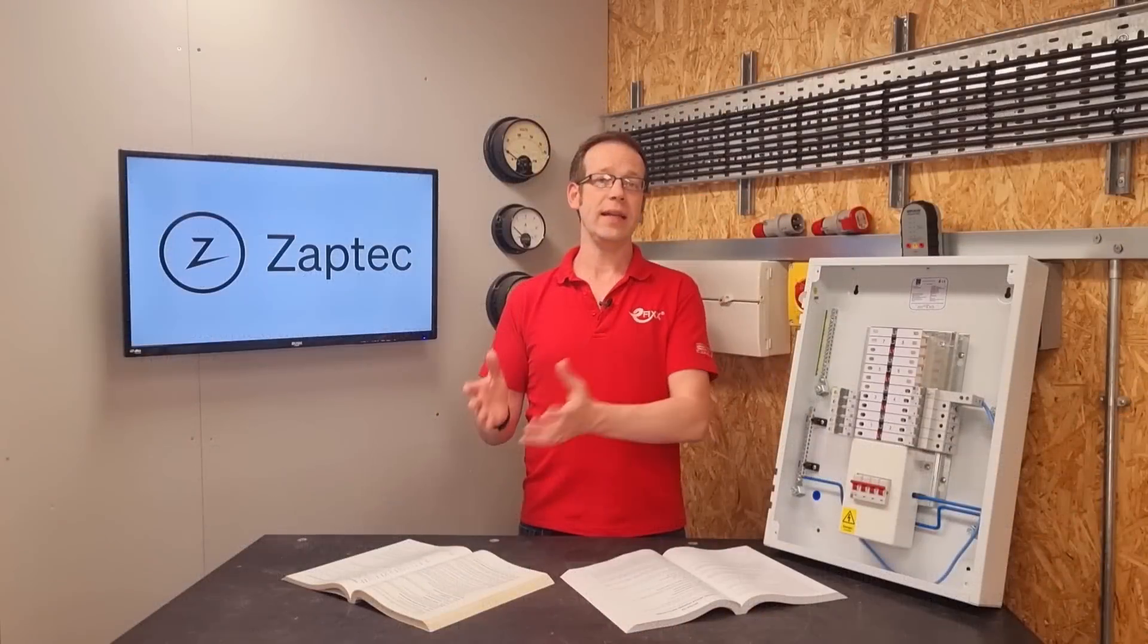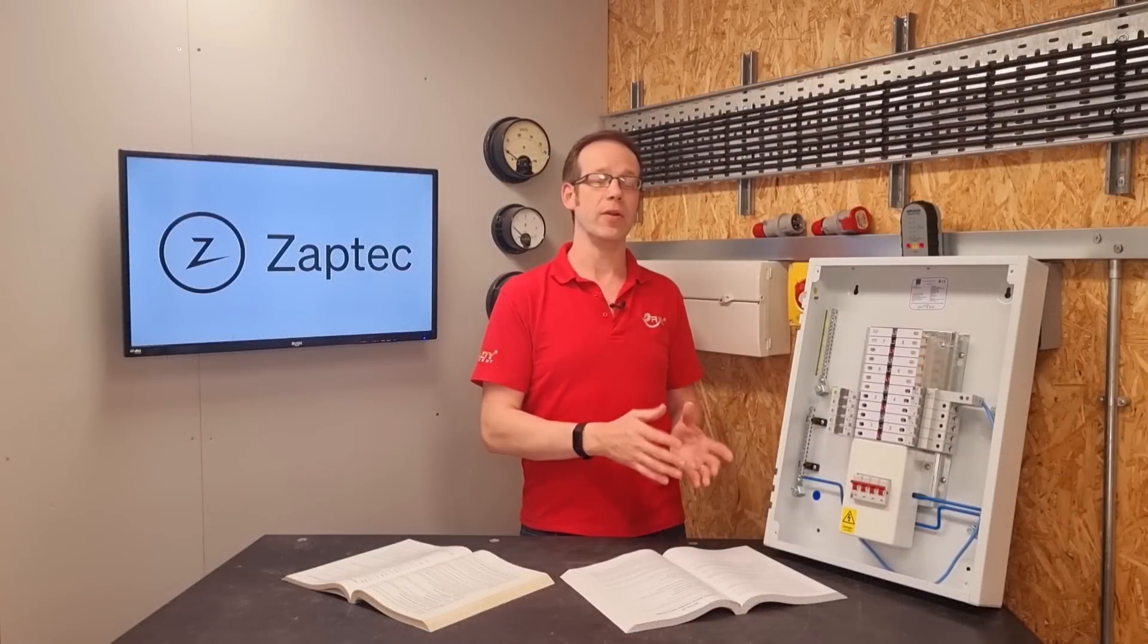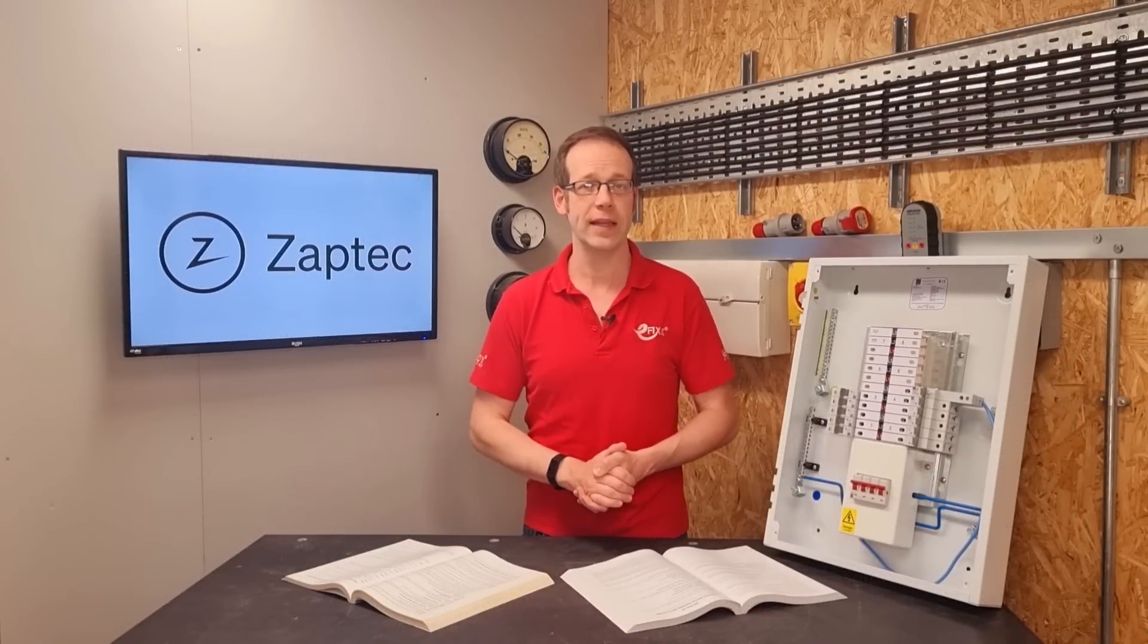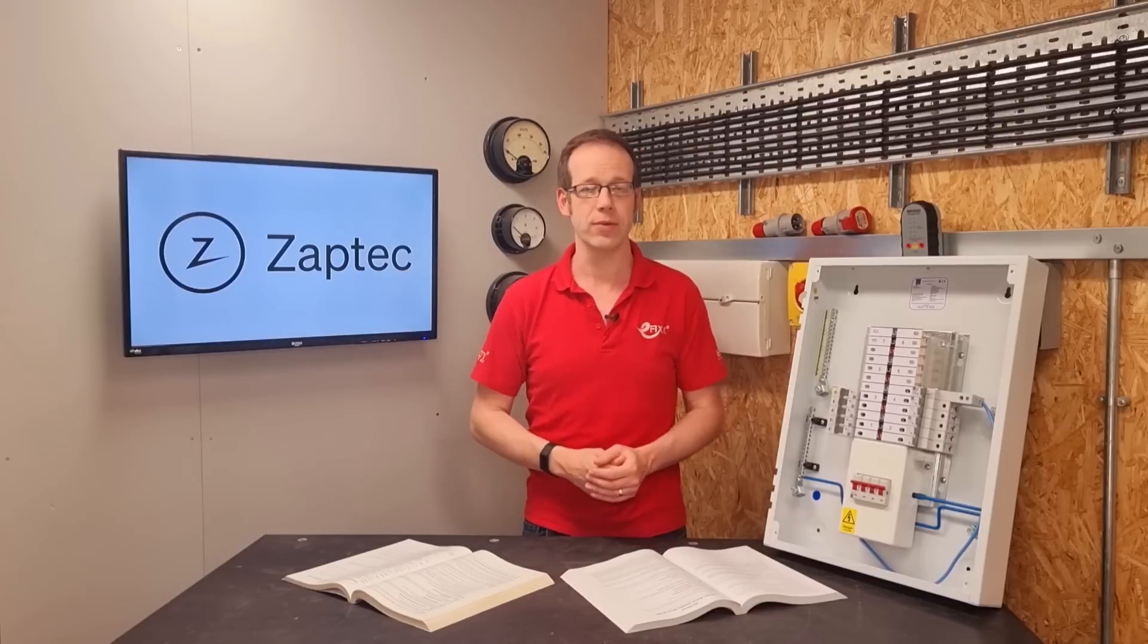So you can't connect the earth terminal on an EV charge point to the PME terminal of a TN-C-S supply if the EV connected to it is likely to charge up outside.